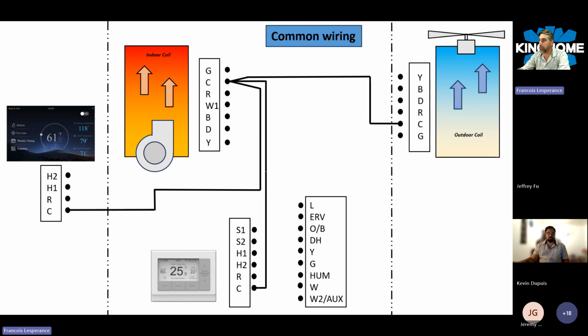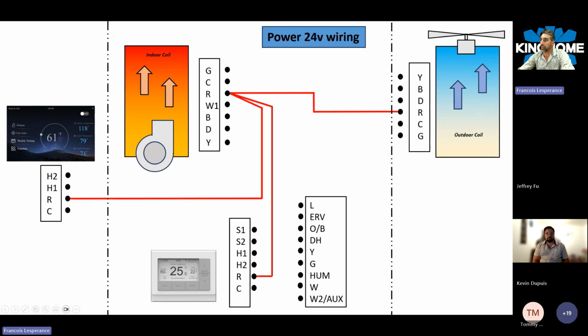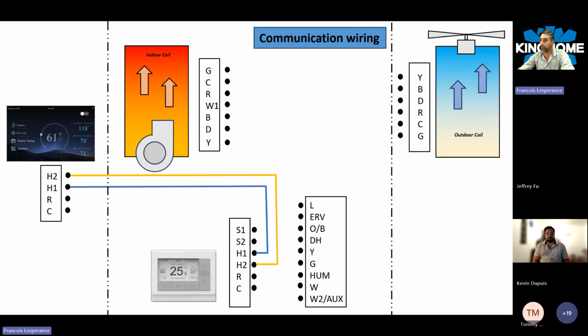Let's start with the first connection that I like to do when I'm wiring everything up, which is the common wire, just making sure you don't forget any common connections. The touchscreen thermostat doesn't have one. The white one, the primary thermostat, has a common over here, as do the outdoor unit and your furnace. Same for the R terminal, your 24-volt power.